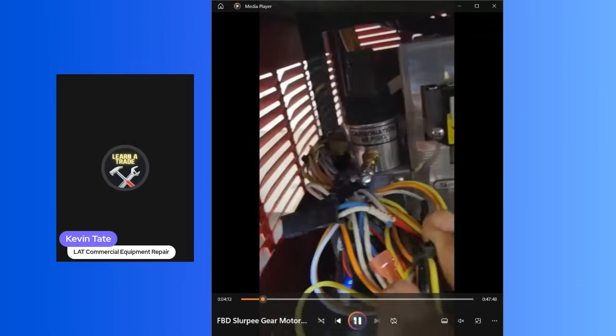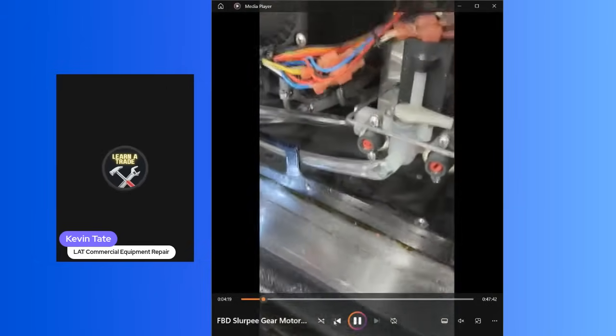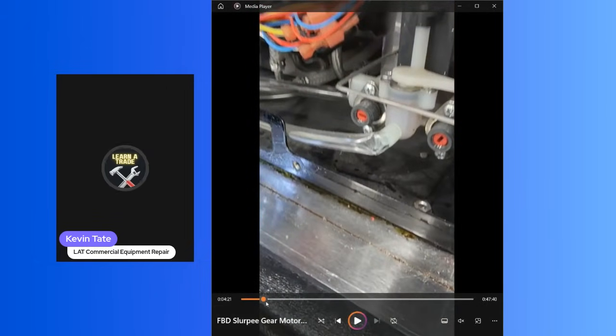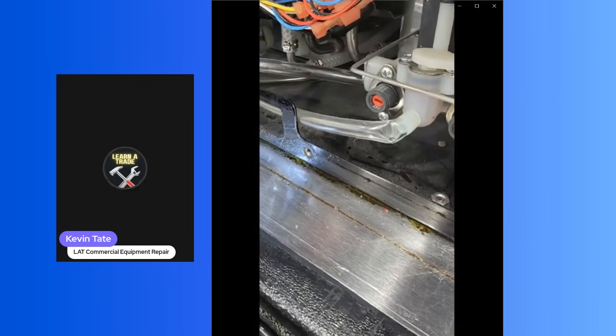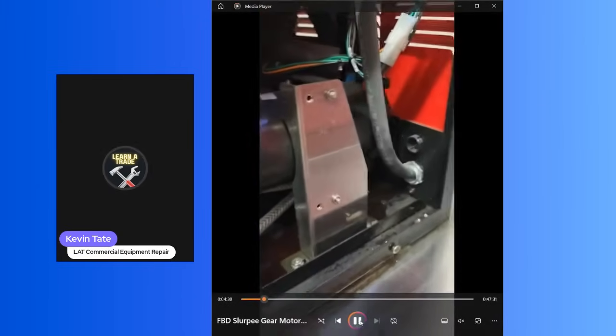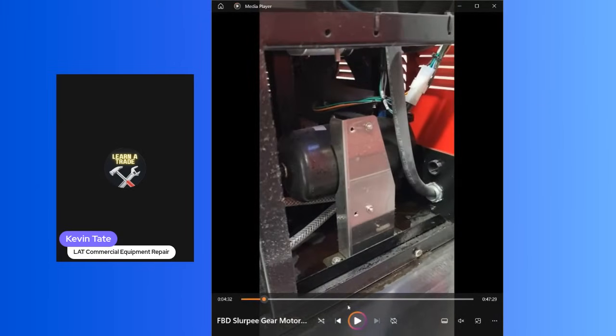And that right there is your active charge. The reason I was testing that, like I said, was to see if I saw any liquid in that line, or if I was getting any liquid through that valve, which I wasn't. So that shows those bladder tanks you're seeing right there are good. We don't have any ruptured bladder tanks.